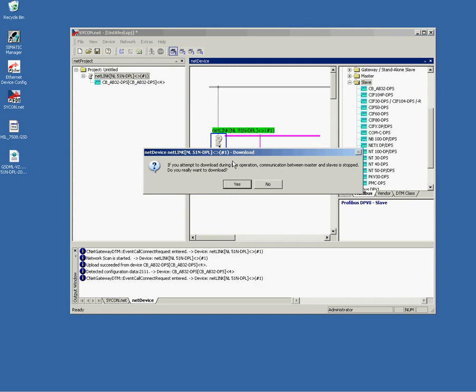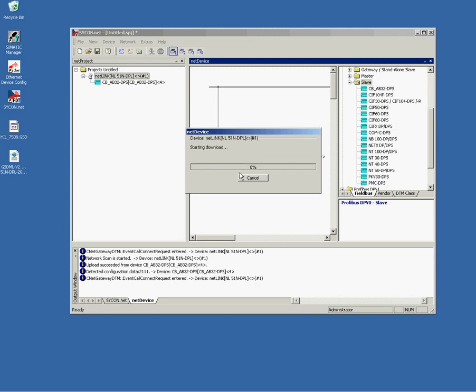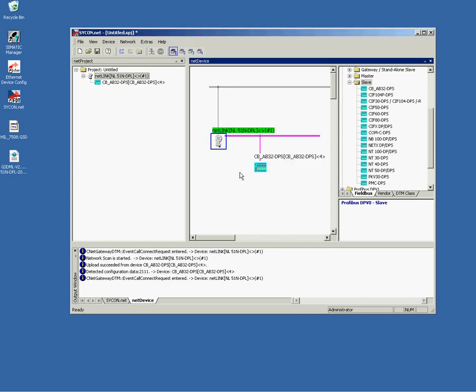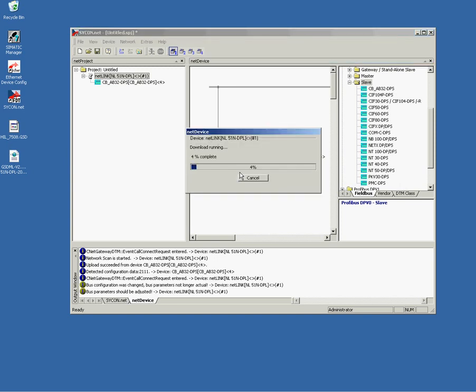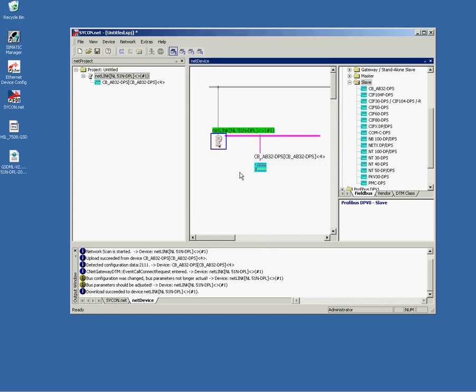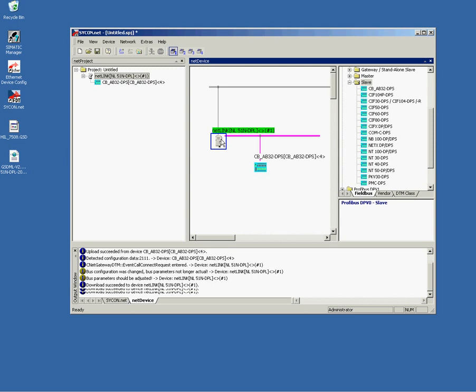Finally, we have to download the Profibus configuration to Netlink. Again, use the right mouse button and choose download from the top-down menu. The software will now prepare the download and downloads the whole configuration in three steps. So, this was all. Let me repeat what we have done so far. We have auto-configured Profibus configuration. We have exported the GSDML file and we have made a download. We are now ready and finished with the Sycon.net software.